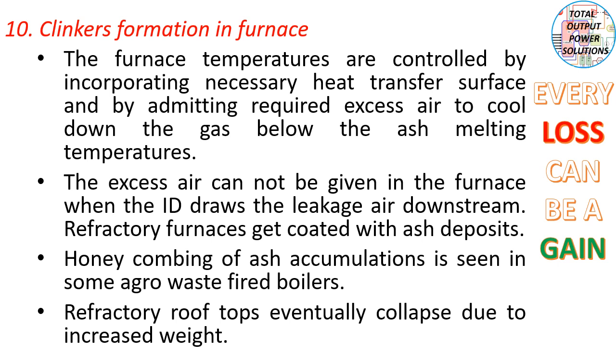Clinker formation in the furnace. The furnace temperatures are controlled by incorporating the necessary heat transfer surface and by admitting the required excess air to cool down the gas below the ash melting temperatures. The excess air cannot be given in the furnace when the ID fan draws the leakage air downstream. Refractory furnaces get coated with ash deposits. Honeycombing of ash accumulations is seen in some agro-waste fired boilers. Refractory rooftops eventually collapse due to increased weight.